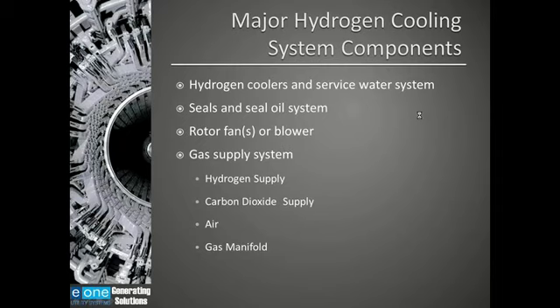Some major parameters that need to be monitored in the hydrogen auxiliary system are the hydrogen supply system. We want to know what the pressure is. Some users will want to know what the flow is. You always want to make sure that you got enough hydrogen on supply for your day-to-day operation. The CO2 supply system, again, we want to know what the pressure is. And it's critical to know the volume of your CO2, because you want to make sure that you've got enough CO2 on hand in the event that you have to purge that generator, and not just during normal maintenance, but in an emergency situation. The rotor fan differential pressure needs to be monitored, generator case pressure, gas temperatures.